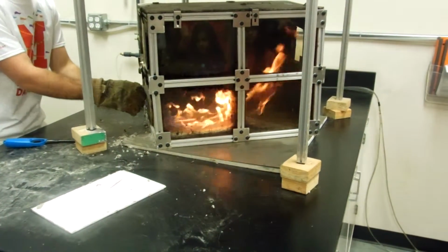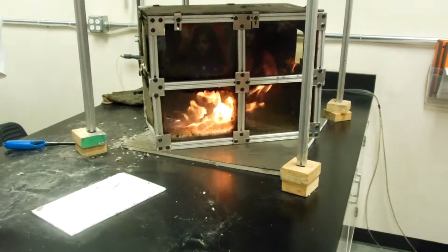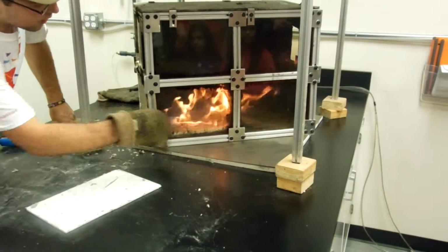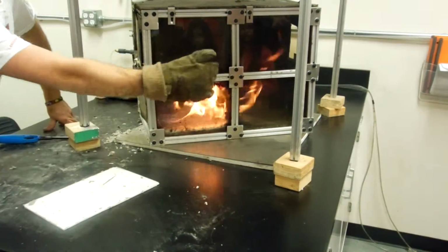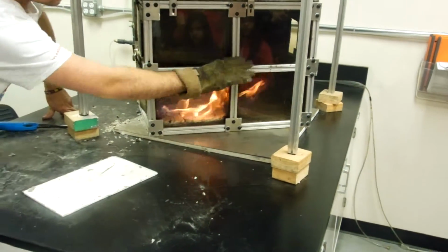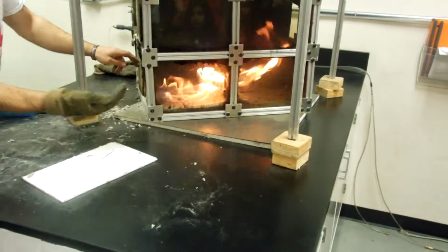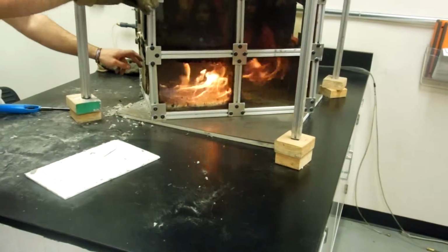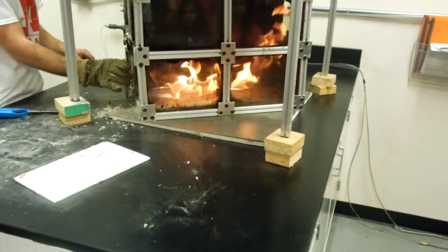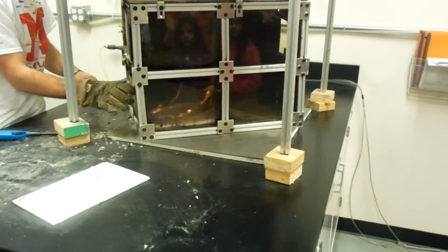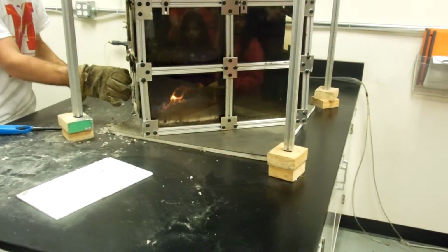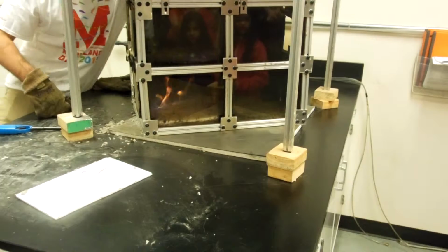And essentially, this is modeling a real fire that happened. I'll explain that with this model I have over here. But fires in here, this is a stairwell. We don't have a floor in between these two levels. So the fire is going to burn in here and then travel up this stairwell and vent out that one side. And the reason this is happening is when this door is closed, there's only one ventilation source for this room, and that is this hole over here.